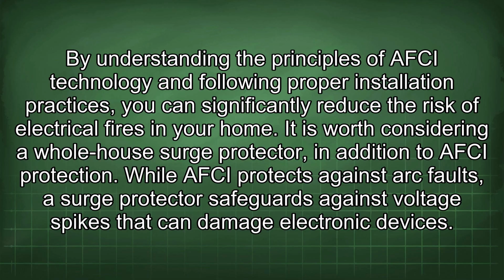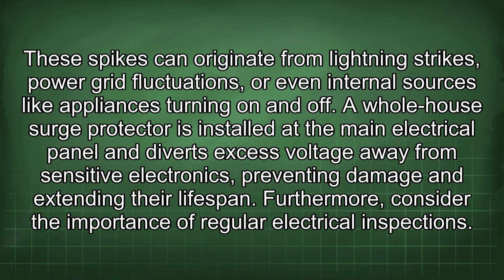It is worth considering a whole house surge protector in addition to AFCI protection. While AFCI protects against arc faults, a surge protector safeguards against voltage spikes that can damage electronic devices. These spikes can originate from lightning strikes, power grid fluctuations, or even internal sources like appliances turning on and off. A whole house surge protector is installed at the main electrical panel and diverts excess voltage away from sensitive electronics, preventing damage and extending their lifespan.